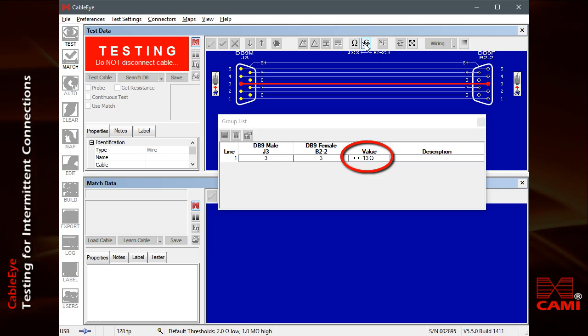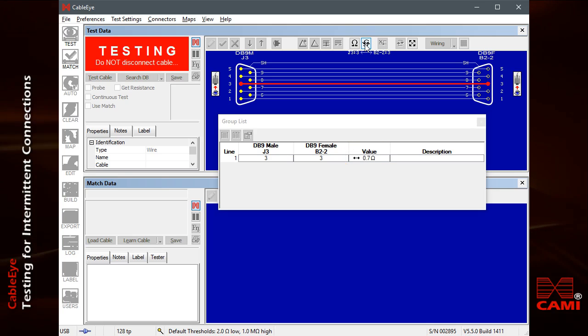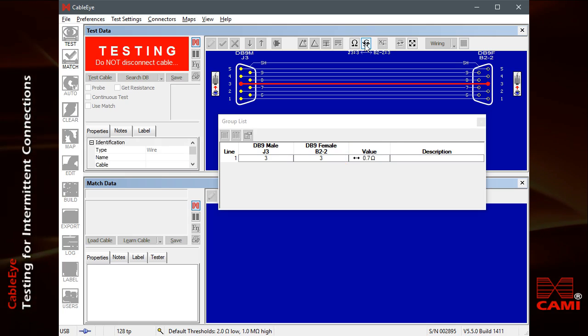We notice that it varies widely and moves well above the 2 ohm threshold for a good conductor. Clearly, we've detected a bad connection.